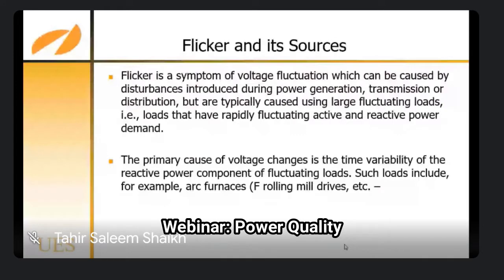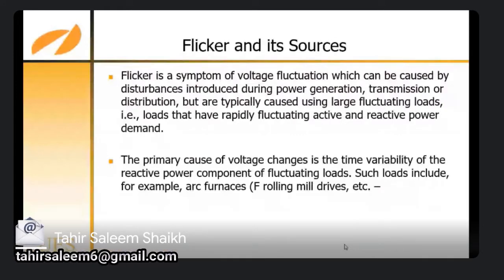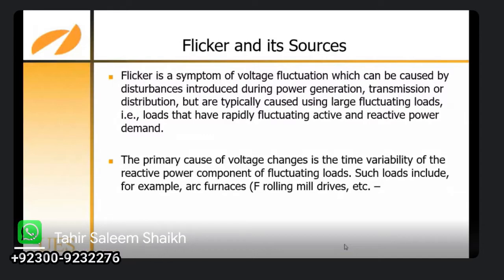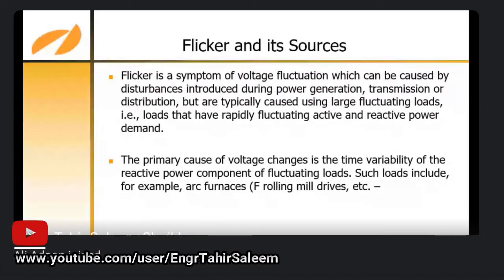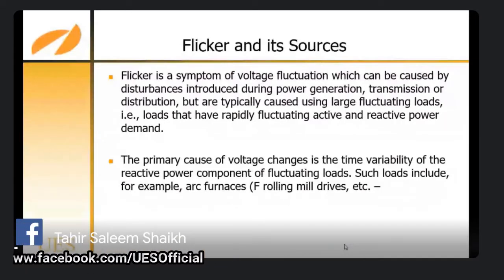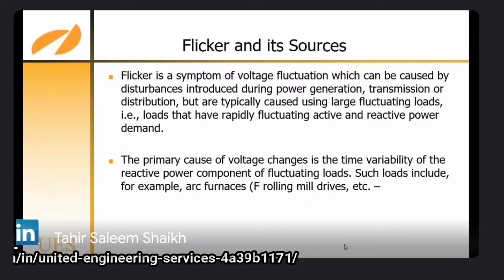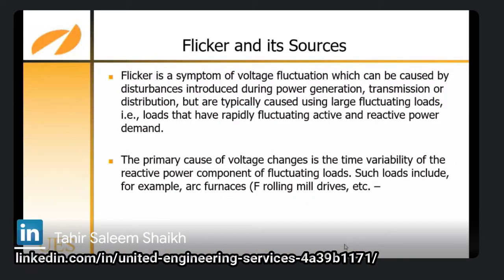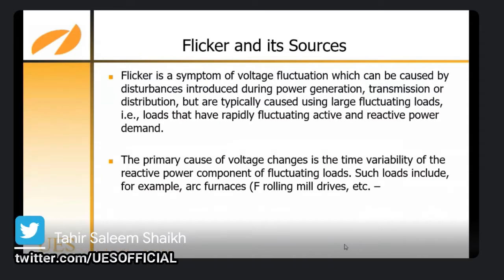Then comes the flicker. Flicker is a symptom of voltage fluctuation, which can be caused by disturbances introduced during power generation, transmission or distribution, but is typically caused by large fluctuating loads that have rapidly fluctuating active and reactive power demands. The primary cause of voltage change is the time variability of the reactive power components of the fluctuating load. Such loads include, for example, arc furnaces, rolling mills, drives, etc.